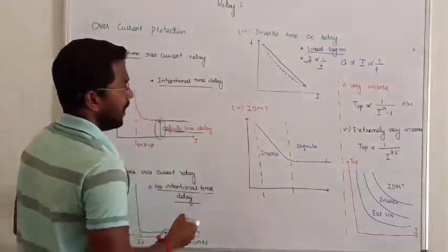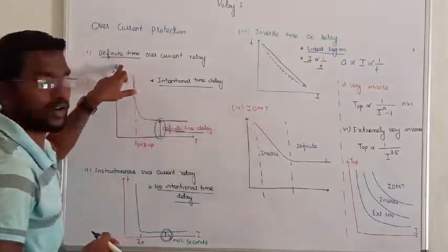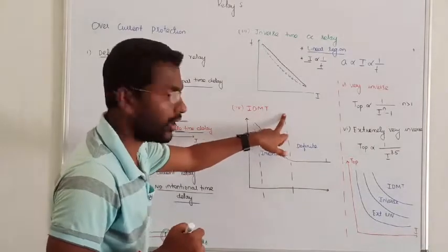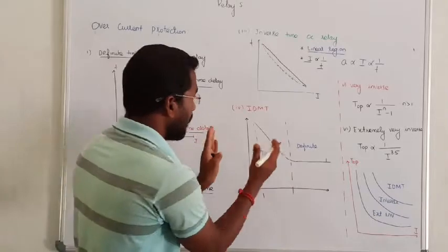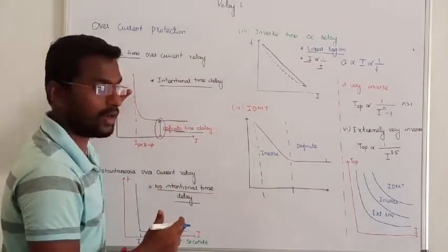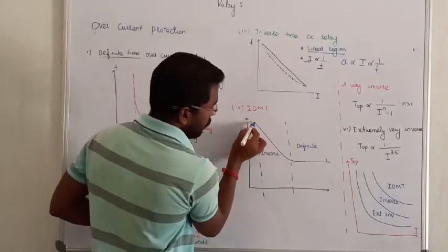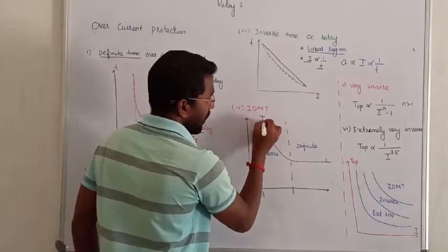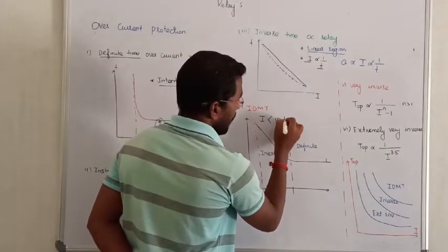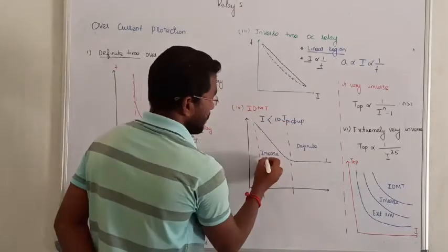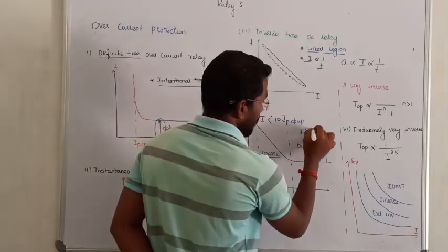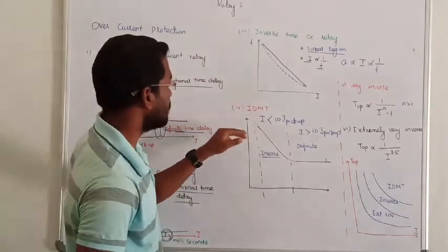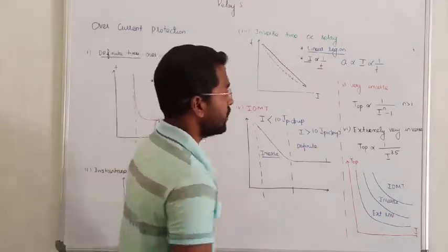Next, the fourth is IDMT — I denotes Inverse, D denotes Definite. So what is the conclusion? Inverse Definite Minimum Time overcurrent relay. It is a combination of inverse relay and definite time overcurrent relay. If the value of current is less than 10 times the pickup current, it acts as an inverse relay. If the value becomes greater than 10 times the pickup current, it acts as a definite time overcurrent relay.